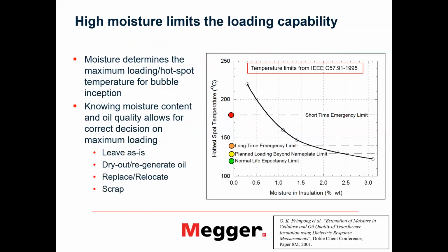Here I would like to illustrate in graphical shape that we have a moisture content in the insulation. So if we have a transformer which is new, with 0.5% moisture content and lower, we can load it pretty hard at short time emergency limit. We can load up to 200 degrees at the hottest spot in the winding.